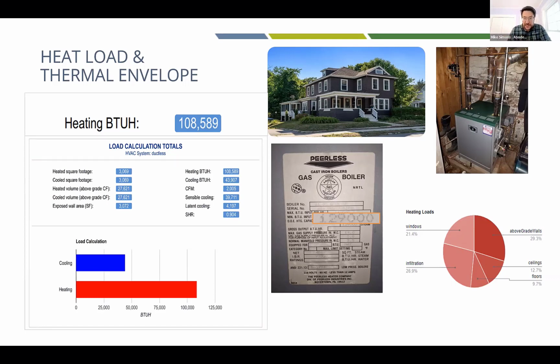All heating systems, if you go look at the label, you'll see the size of that system. One follow-up point: you should never size a heat pump system based on the capacity of the existing equipment in the basement or utility room, because it may not have been properly sized the first time. And as we're about to see, the performance of a home can change as well.